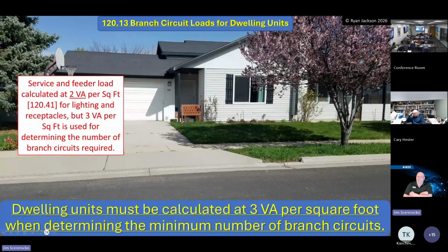And I was showing them this yesterday, that the service and feeder load is calculated at 2 volt-amps per square foot for the lighting and receptacles, but 3 volt-amps per square foot is used to determine the number of branch circuits required. So because of the LEDs, the allowance of the 10 amp circuit breaker in the 2023 code, and also the fact that we have 14-2 copper clad aluminum conductors available in the 2026. It was not available in the 2023. They kept it out. A certain person kept it out. But Copperweld came back and pushed really hard to have it put in. And so you can put 8 amps on that.